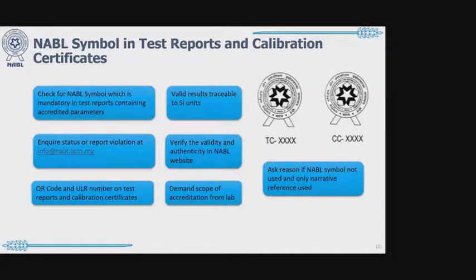If the test report which you get from the laboratory does not have the NABL symbol or the ULR number or QR code, you have every right to ask the laboratory why it is not so. Whenever you approach a laboratory and get a quote for testing, insist on the scope of the laboratory, because the laboratory is obliged to give you the scope of accreditation for which it is accredited. Then you can check whether your product is in the accredited scope or not, and whether the test method against which you want to get tested is in the scope or not. All those things you have the right to ask the laboratory.